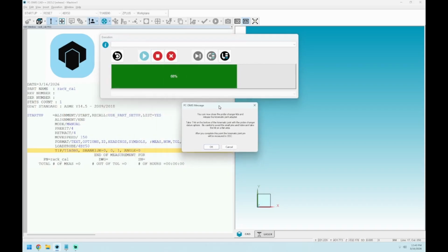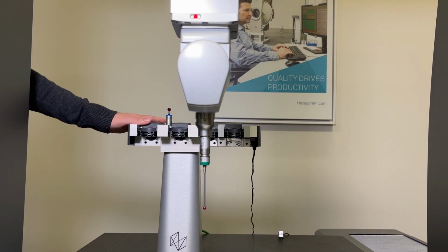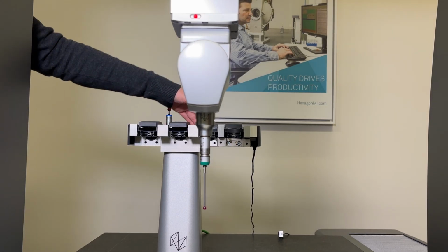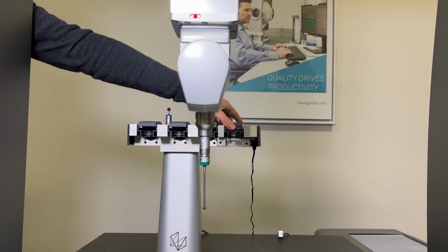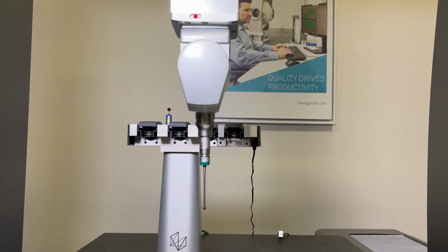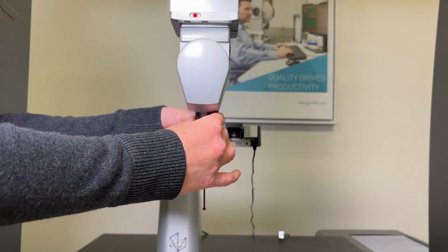Next, it will prompt you to close all of the probe changer lids and release the kinematic joint adapter. It also says to take one hit on the bottom of the kinematic joint with the probe changer datum sphere. You are not taking this hit with the lock that protrudes from the kinematic joint.